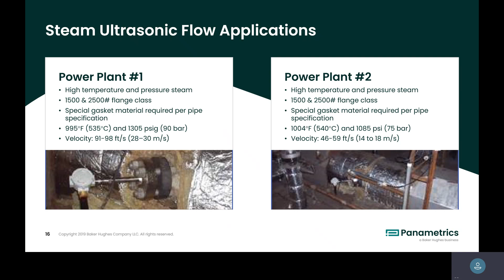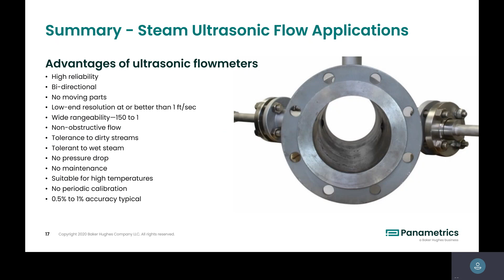To summarize what we've covered: reliability, bidirectional measurement, wide rangeability at the low end, no obstruction in the flow, tolerance of wet steam, suitability for high temperature, and no maintenance. Accuracy is typically about 0.5 to 1% that you can expect from an ultrasonic meter, so it provides strong capabilities overall.